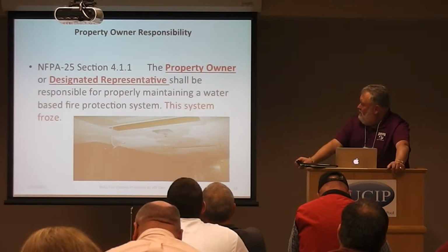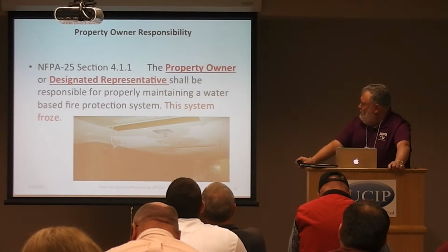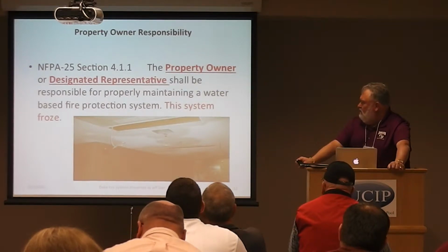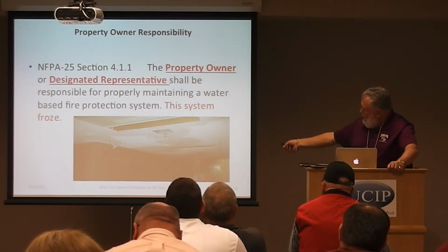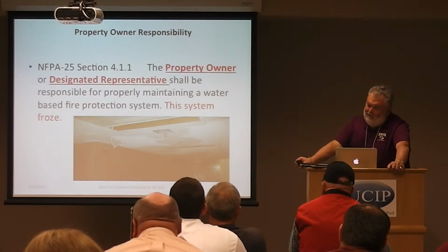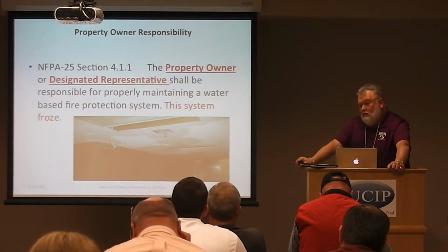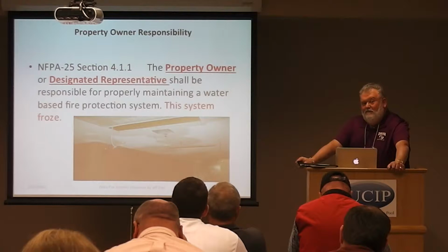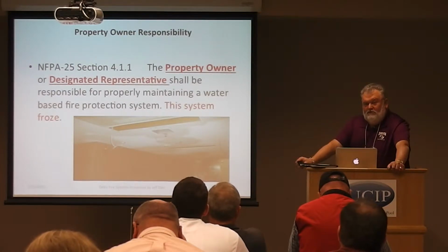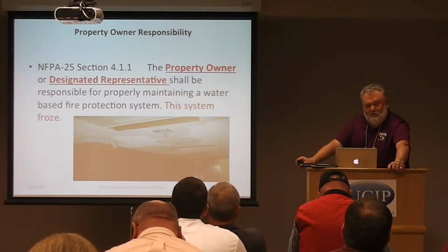Okay, now who is really responsible? In NFPA 25, section 4.1.1, very clearly states the property owner or his designated representative shall be responsible for properly maintaining the water-based fire system. I don't know if you can really see this picture here too much, but that's a school that actually had turned off the heat over winter recess and found out that wasn't really a good idea with the wet system to turn off their heat. Been a lot of major damage, as you can see there.